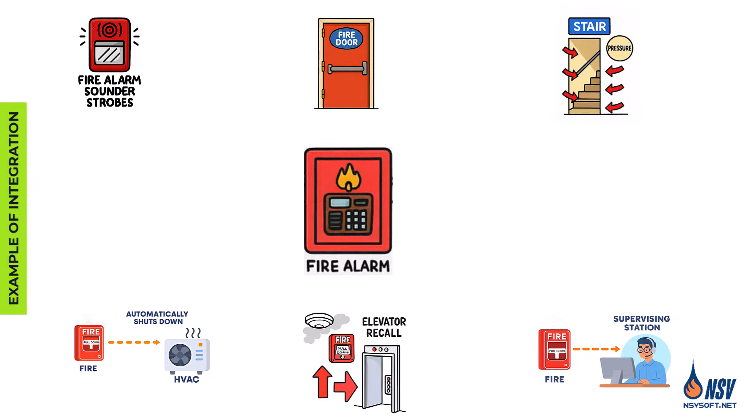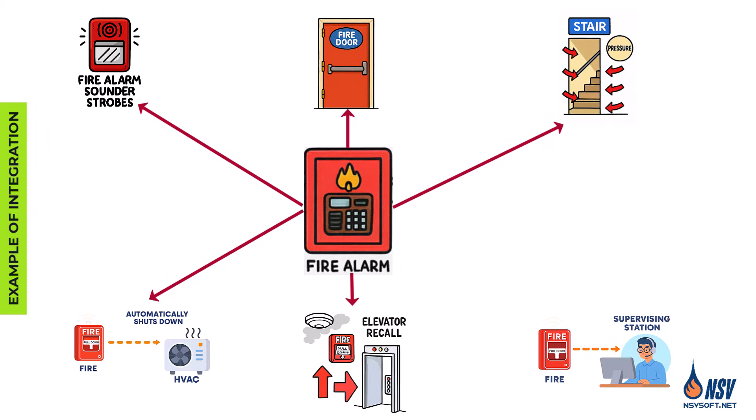A typical example of system integration is when a smoke detector activates and triggers multiple coordinated actions. The evacuation signal sounds throughout the building, exit doors unlock, stairwells become pressurized, the HVAC system shuts down, elevators are recalled to the exit level, and the alarm signal is automatically transmitted off-site.